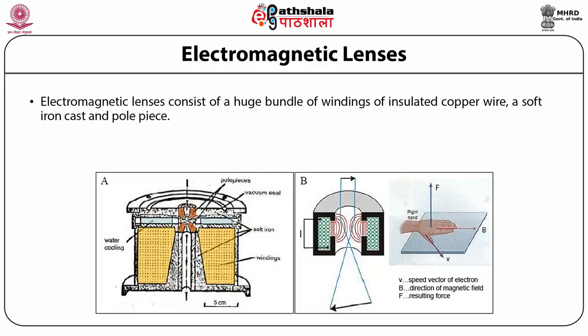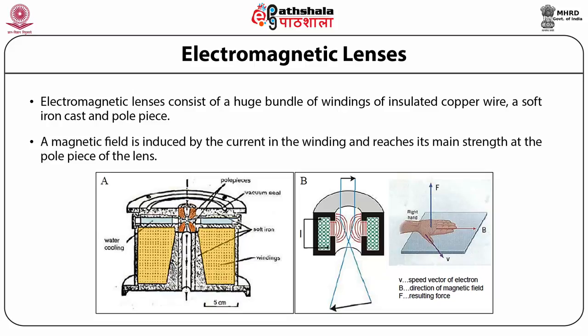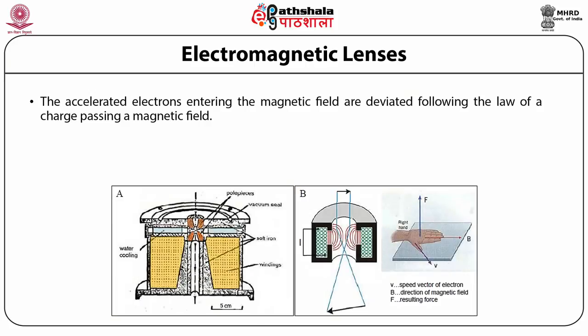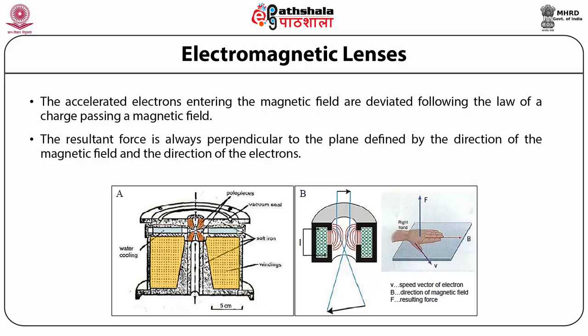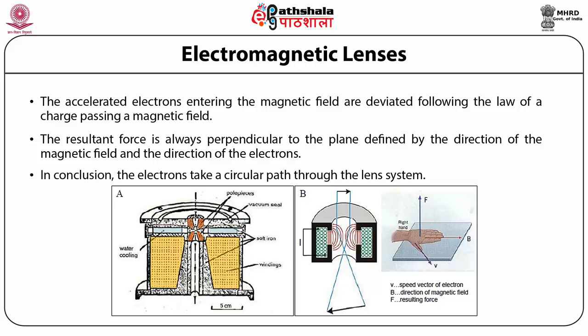Electromagnetic lenses consist of a large bundle of windings of insulated copper wire, a soft iron cast, and a pole piece as shown in the figure. A magnetic field is induced by the current in the winding and reaches its main strength at the pole piece of the lens. The accelerated electrons entering the magnetic field are deviated following the law of a charge passing through a magnetic field, and the resultant force is always perpendicular to the plane. The electrons take a circular path through the lens system.